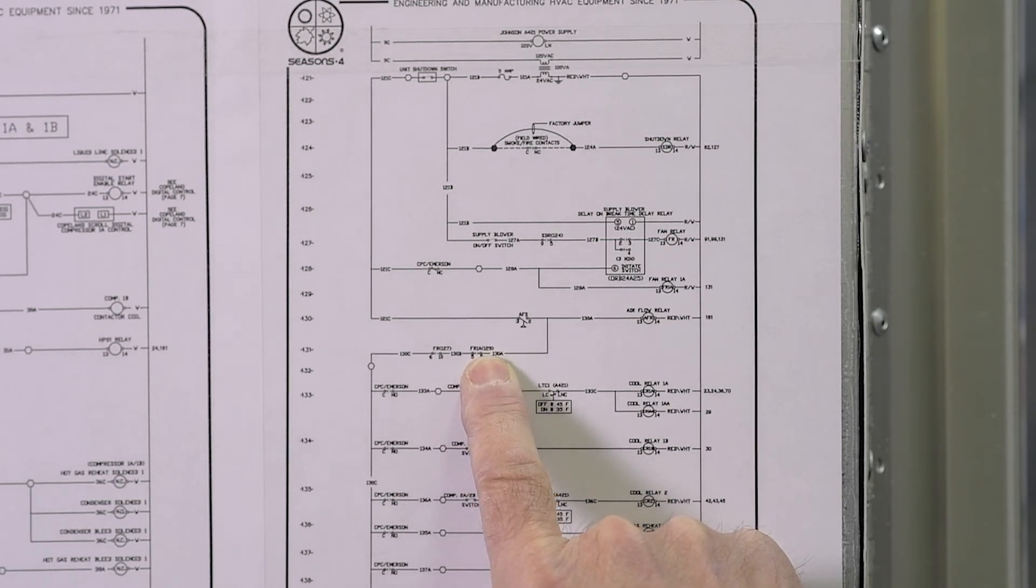The number in parentheses after FR1A, 128, indicates where the coil is for that set of contacts. If I go back over to the line numbers and up to 128, I'll slide over and I can find the coil for that set of contacts.